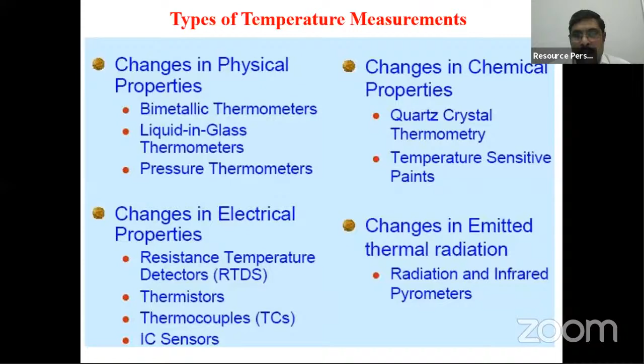First, we look at change in physical property — here is the bimetallic thermometer. This is a standard temperature measuring device, widely used, especially in process control areas. This thermometer consists of two metallic strips with different thermal expansion coefficients, bonded together using a high thermal conductivity cement. When this strip is exposed to an unknown temperature, because of the difference in thermal expansion coefficients, the strip will bend.